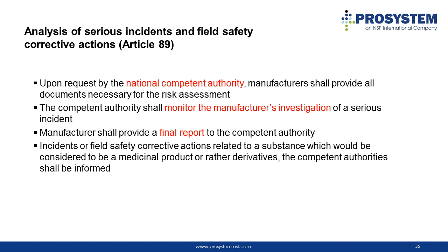If the device is under investigation, no changes may be made to the product. At the request of the competent authority, manufacturers shall provide all documentation necessary for risk assessment. The competent authority monitors the investigation of a serious incident by the manufacturer. Once the manufacturer has completed the investigation, the final report should be submitted.